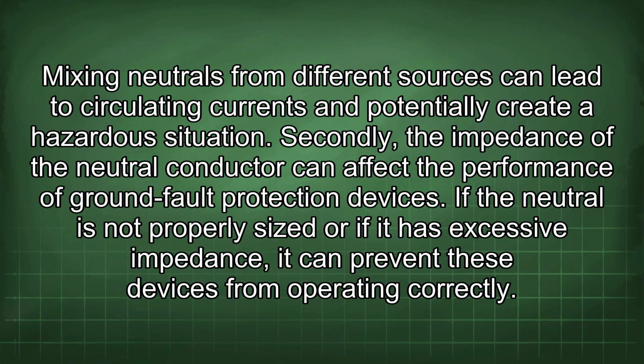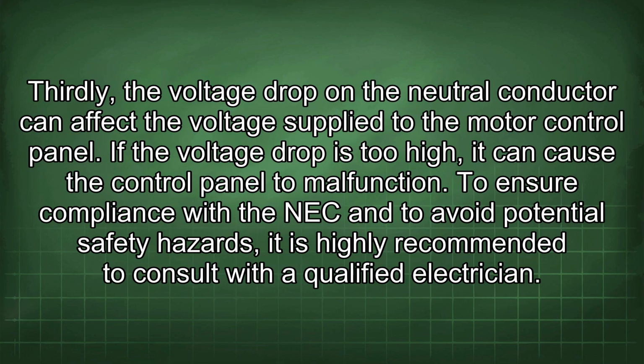Secondly, the impedance of the neutral conductor can affect the performance of ground fault protection devices. If the neutral is not properly sized or if it has excessive impedance, it can prevent these devices from operating correctly. Thirdly, the voltage drop on the neutral conductor can affect the voltage supplied to the motor control panel. If the voltage drop is too high, it can cause the control panel to malfunction.